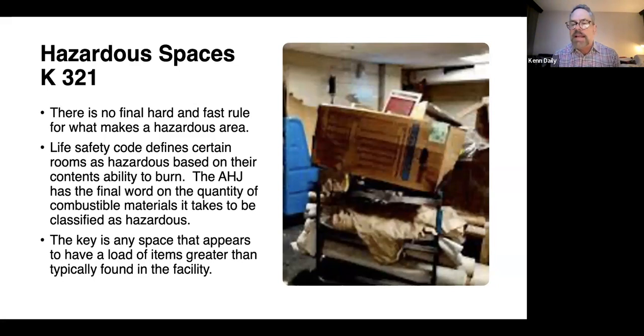Those are the doors that, in most cases, are permitted to actually have a magnetic hold open device to hold them open, and it closes when the smoke alarm or the fire alarm is initiated. So the expectation is that they want that door closed because the hazard is there. It's for storage of stuff. As I showed you earlier in your leading tags, K-tag 321 is where you inappropriately hold it open with a wedge, plastic or wood, or, what's worse, you shove a washcloth in the lock set so the door doesn't latch, or I've seen duct tape and wires and hangers and whatever. Holding the door open inappropriately will get you in a lot of trouble as well. The load of that room is pretty high.